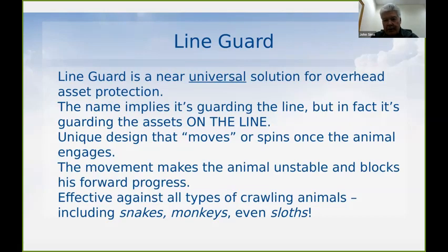It's not applied or used like an insulator, so there's no difference to the line or its conduction whether it's got a series of rollers on it or not. It doesn't affect electrical flow or insulation resistance, because you've already got established air gaps, and you're not any closer by putting Line Guard on it. So Line Guard is a fairly universal solution for overhead assets.